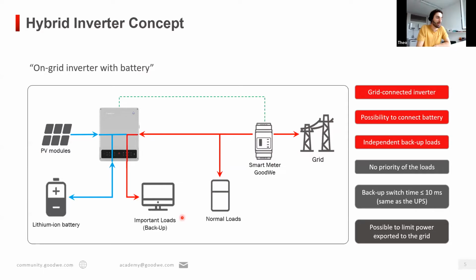Something different with our hybrid inverter is that in addition to the PV modules that you can connect here, you can also connect the battery. So here you can both get energy and store energy into this lithium-ion battery. But we also offer a backup port on these inverters. So you basically have 2 AC outputs, one that goes directly to the grid where you connect your normal loads, but also a second AC output where you can connect some backup loads.